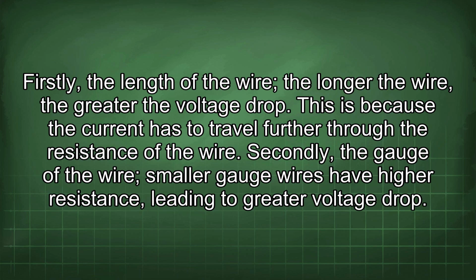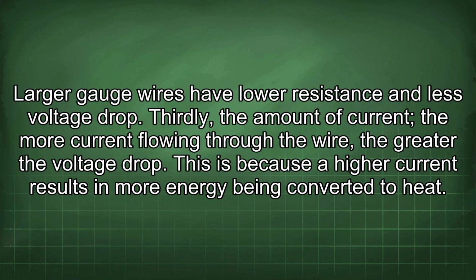Firstly, the length of the wire. The longer the wire, the greater the voltage drop. This is because the current has to travel further through the resistance of the wire. Secondly, the gauge of the wire. Smaller gauge wires have higher resistance, leading to greater voltage drop. Larger gauge wires have lower resistance and less voltage drop. Thirdly, the amount of current. The more current flowing through the wire, the greater the voltage drop. This is because a higher current results in more energy being converted to heat.